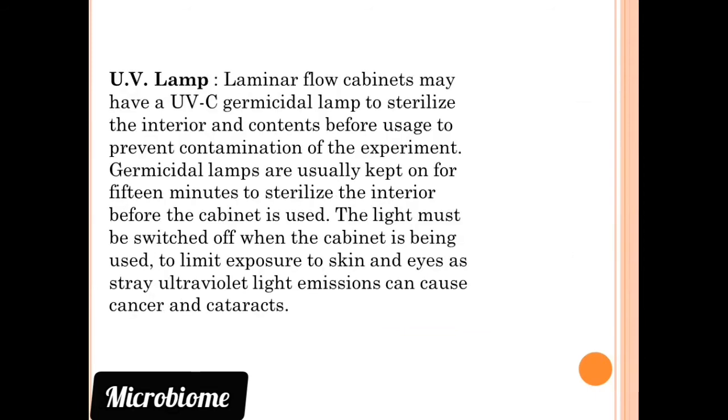Now next one is the UV lamp. What is the function of the UV lamp? Laminar flow cabinets may have a UVC germicidal lamp to sterilize the interior and contents before use to prevent contamination of the experiment. Germicidal lamps are usually kept on for 15 minutes to sterilize the interior before the cabinet is used.